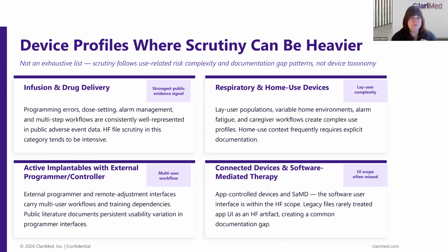So I wouldn't necessarily jump straight into doing a new summative or an IFU change, but they often contain a lot of instructional information. And if that's unique to your product, then yes, I would think you would probably need to do some validation work with it. But if it's a product that's very similar to another product and the labeling's very similar, then it might be that it could be avoided. I don't know whether, Angelina, you have an opinion on that.